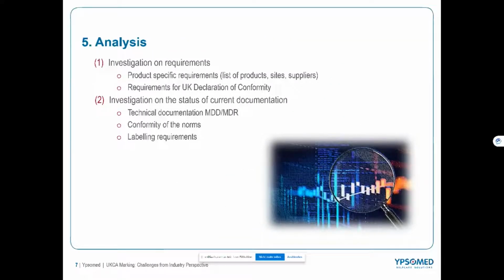So for the analysis, we made some investigations on the requirements, so product-specific requirements, and also the requirements for the UK Declaration of Conformity. And we also investigated the status of our current documentation: the technical documentation under MDD and MDR, the conformity of the norms, and also the labeling requirements, what we have and what we need to meet to get the UKCA mark for our device. And here is our focus and process.